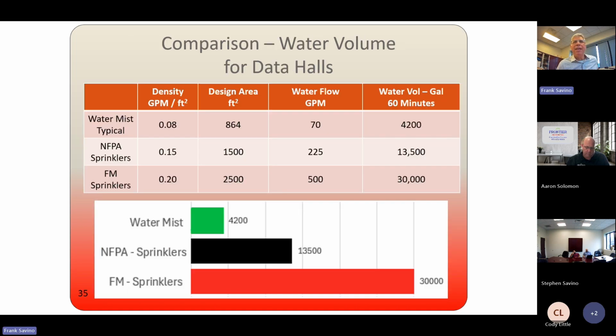But this is a really informative table that you see here. So let's take a look at it. This is for data halls. The typical density is 0.08 gallons per minute per square foot on a water mist system. That's a closed head system. Your design area, which is 6 nozzles, would be 864 square feet. Your total flow for those 6 nozzles is 70 gallons per minute, and over 60 minutes, which is the required duration, you would have to allow for a total of 4,200 gallons. If you're going to have a water tank, you would need 4,200 gallons of water in a tank.